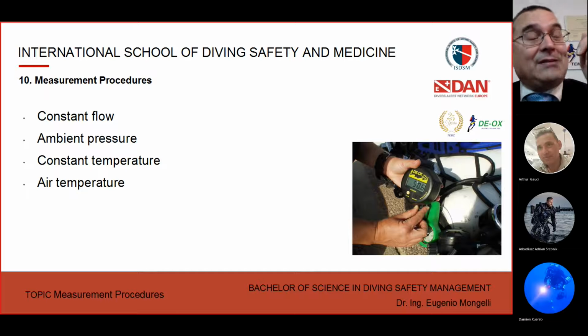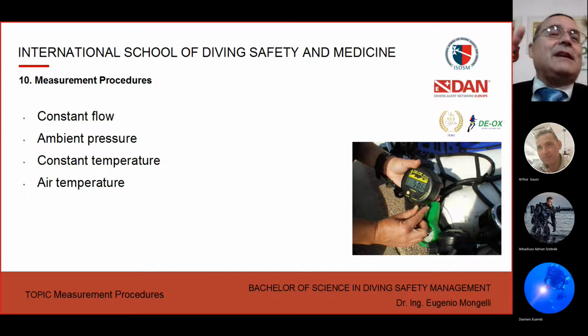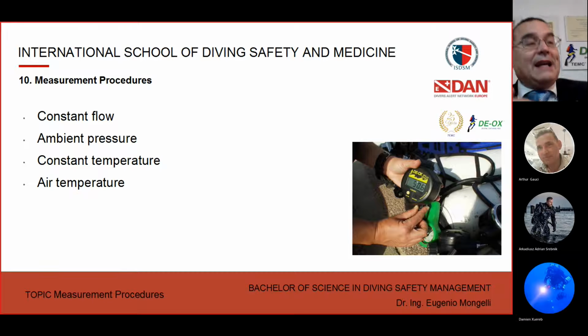I said, yes, it's correct. But are you sure that you flow the sensor for the calibration with the same gas? Are you sure that the temperature was right? And I gave them the tip. The tip is to use compressed air coming from a cylinder. Then you flow this synthetic air into the analyzer. You don't use the ambient air, full of humidity. You use the gas as a calibration gas, and you assume that you are at 21%, not 20.3, because you use a dry gas coming from the cylinder. You have a flow that can chill the sensor. Then you have the same flow, and in this way you make a very good calibration with air.